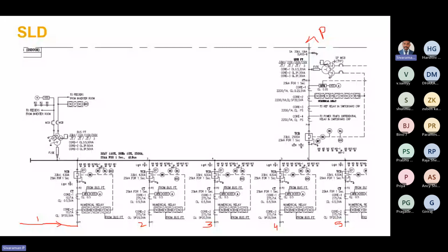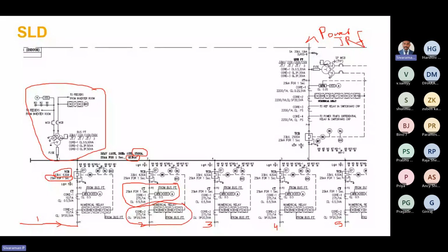This will go to the power transformer. Okay, so here you can see it is a 33 kV, 630 ampere VCB, vacuum circuit breaker. It has a short-circuit capacity of 25 kiloampere for 1 second. This is the bus bar rating, 2500 ampere aluminum bus bar. This is the PT, which is used for instrumentation purposes. These are all the CTs. This is the CT for monitoring purposes. This is the CT for protection purposes.